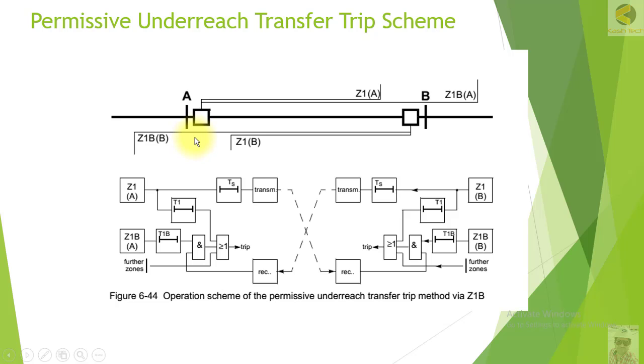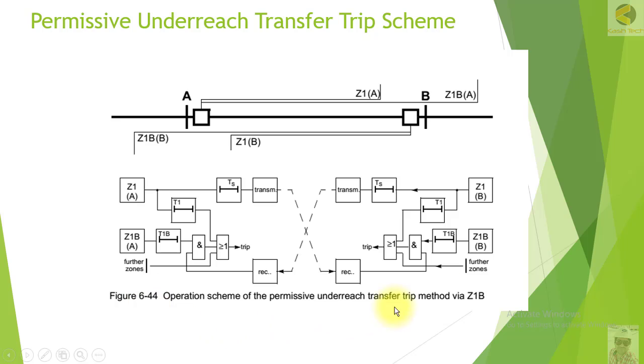As soon as the relay at Station A receives the permissive signal, it will check whether the fault is also in the forward direction Z1B. If Z1B is picked up, then this relay will also trip immediately at Station A. In this way, the relay at Station A will not wait for Zone 2 time, which is 300 to 400 milliseconds, but will trip immediately.